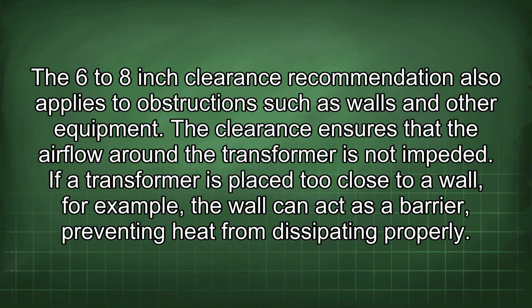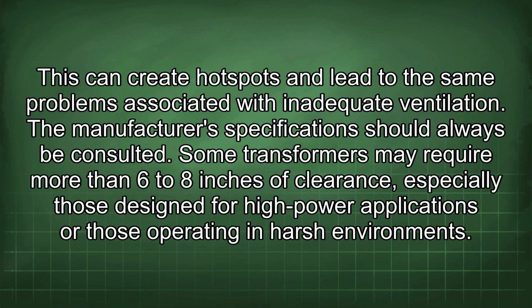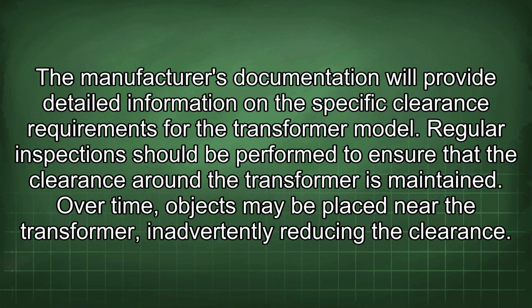If a transformer is placed too close to a wall, for example, the wall can act as a barrier, preventing heat from dissipating properly. This can create hotspots and lead to the same problems associated with inadequate ventilation. The manufacturer's specifications should always be consulted. Some transformers may require more than 6 to 8 inches of clearance, especially those designed for high-power applications or those operating in harsh environments. The manufacturer's documentation will provide detailed information on the specific clearance requirements for the transformer model.